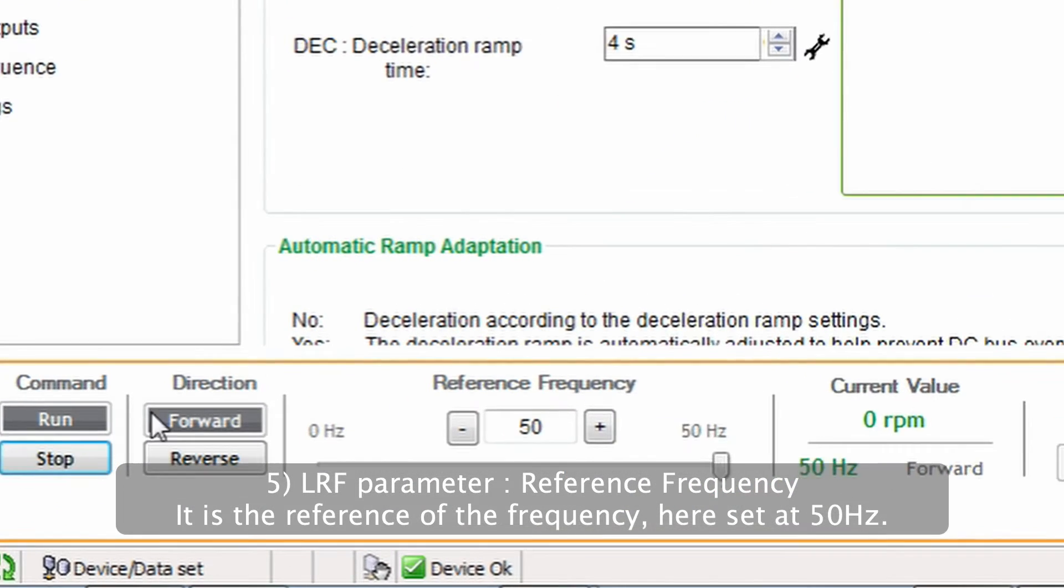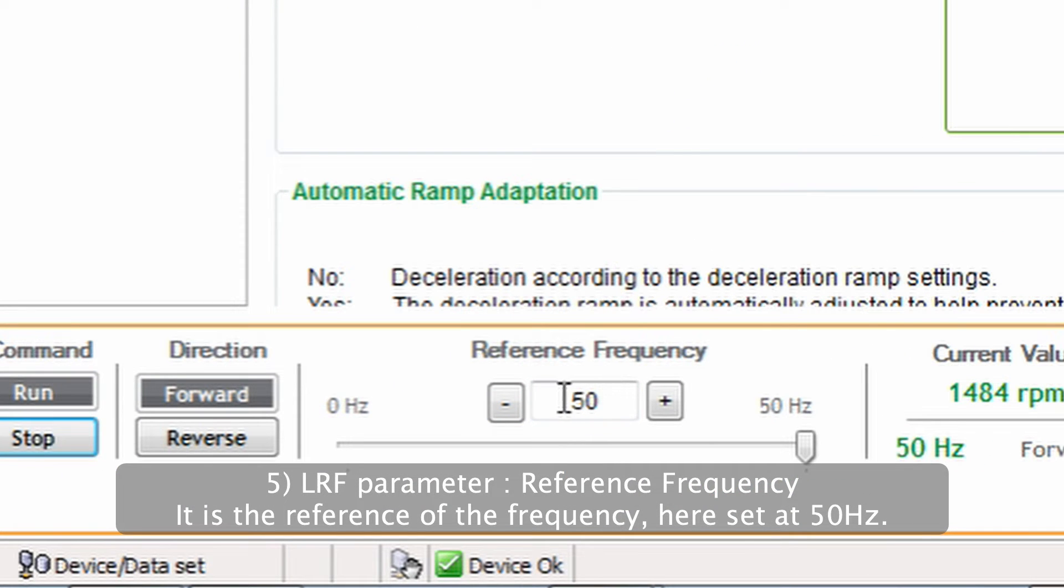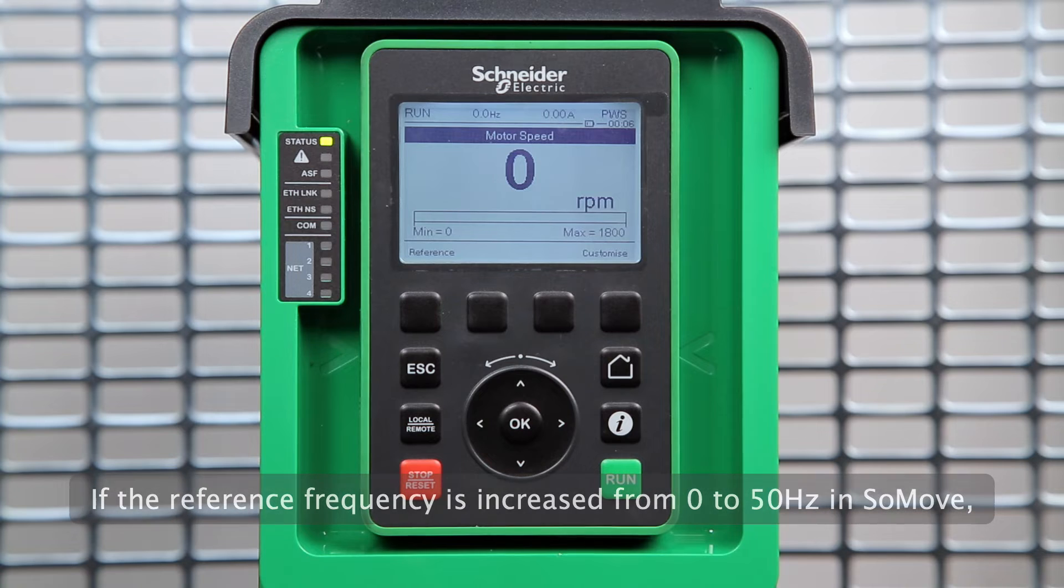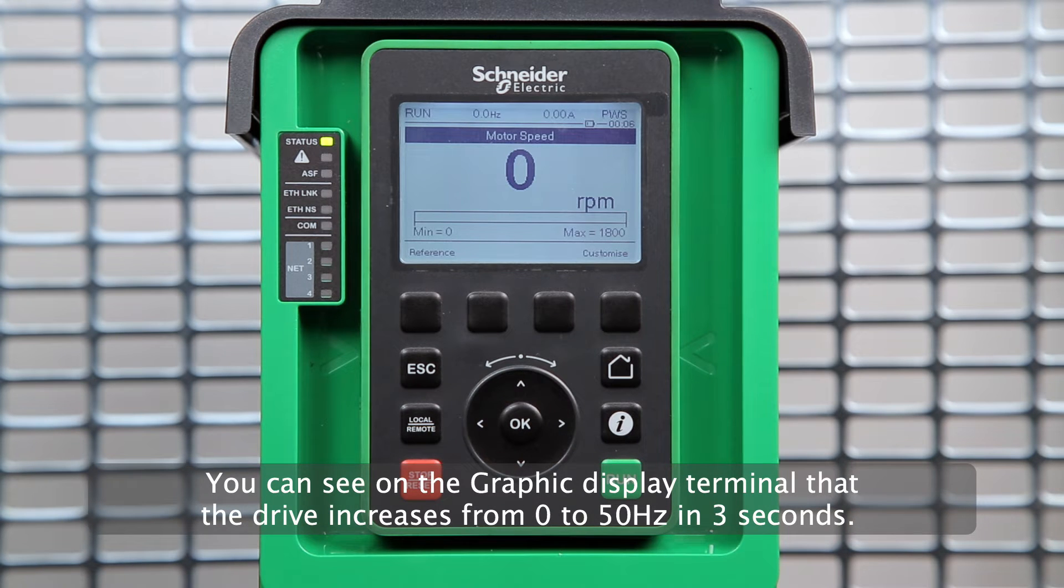Number 5: LRF parameter, reference frequency. It is the reference of the frequency. Here, set at 50 hertz. If the reference frequency is increased from zero to 50 hertz in SoMove, you can see on the Graphic Display Terminal that the drive increases from zero to 50 hertz in three seconds.